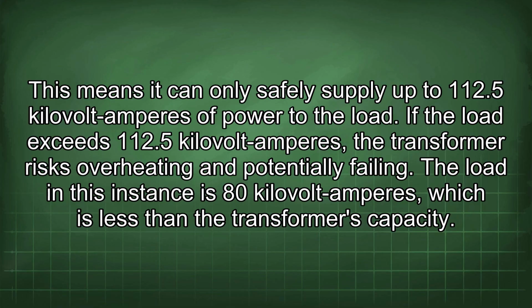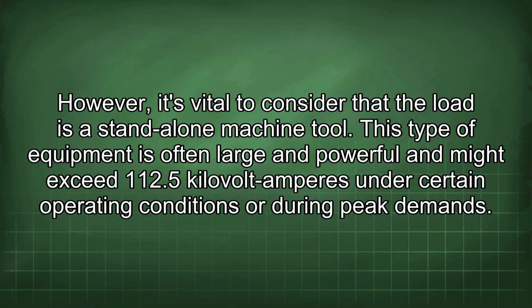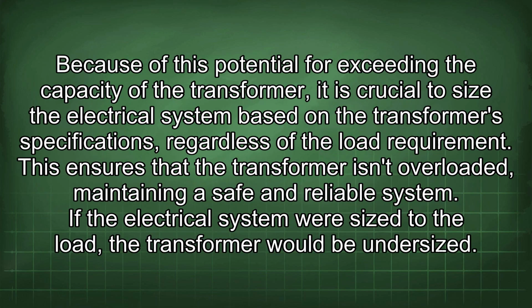The load in this instance is 80 kVA, which is less than the transformer's capacity. However, it's vital to consider that the load is a standalone machine tool. This type of equipment is often large and powerful and might exceed 112.5 kVA under certain operating conditions or during peak demand. Because of this potential for exceeding the capacity of the transformer, it is crucial to size the electrical system based on the transformer specifications regardless of the load requirement. This ensures that the transformer isn't overloaded, maintaining a safe and reliable system.